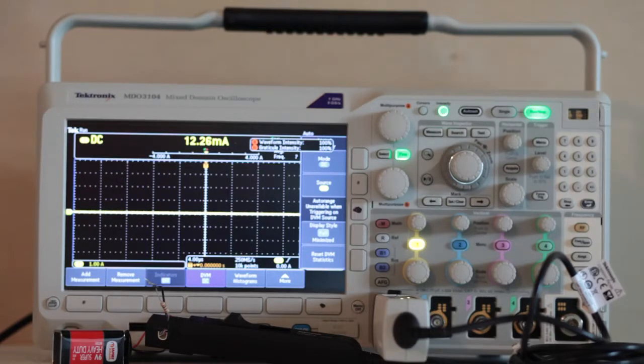The Tektronix TCP0030A current probe is essentially a clamp-on ammeter. It is very sensitive, and as a consequence it has to be degaussed periodically. This is because the jaws can act as a permanent magnet and become magnetized. Then any measurements will be invalid.